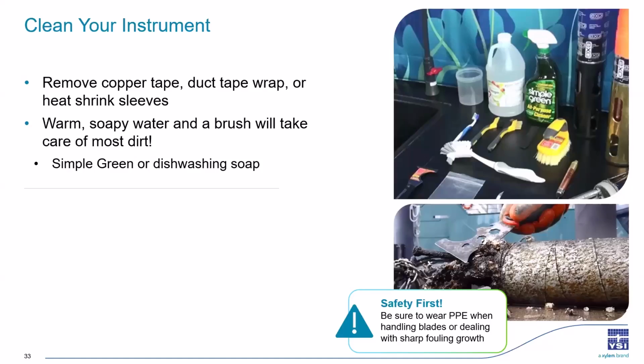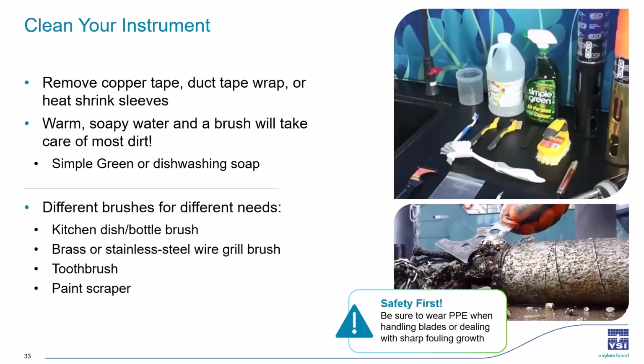So first off, warm soapy water will remove most of the dirt. You can just use Simple Green spray or a few drops of dish soap as well. You can see Simple Green spray is one of those spray bottles up there in the photo. And then if you need to do some scrubbing, you can use different brushes for different things. A kitchen brush or a bottle brush is really helpful to reach down into the sensor guard and really clean sediment down out of there.